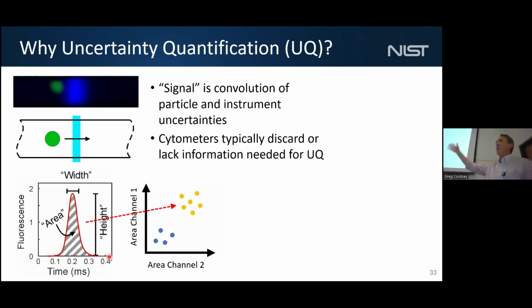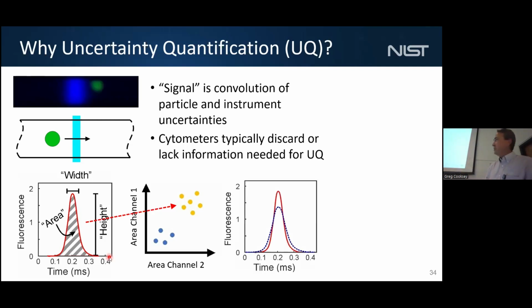for each object of measurement, put that on a scatter plot showing you maybe one biomarker versus another biomarker, or in the case of just scattered single color light that's not fluorescent transmission, you can estimate the size of a particle. So in forward scatter, that's typically used to estimate size. And so here now you can understand 2 different populations based on the characteristics of extracting those metrologies.